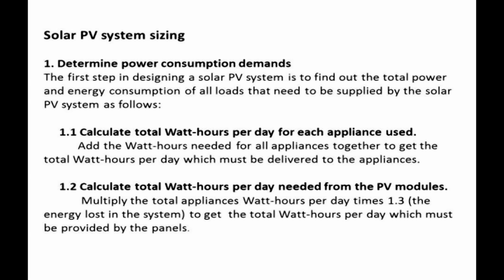Step 1.2: Calculate total watt-hours per day needed from the PV modules. Multiply the total appliances watt-hours per day by 1.3 — accounting for energy lost in the system — to get the total watt-hours per day which must be provided by the panels.